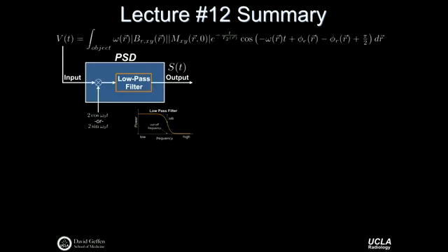And the next step that we worked through was something like this, where we said, well, we've got this rather lengthy voltage expression, but we learned about phase-sensitive detectors. If we multiply by a known carrier frequency, and this is done all the time in signal processing, when you know that there's a principal frequency of interest, in this case the Larmor frequency, we're basically just multiplying by a function that looks like the Larmor frequency. And applying this low-pass filter, if you remember, we had a really high-frequency component term and then a substantially lower frequency term.